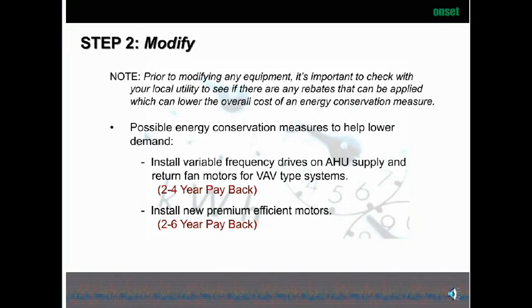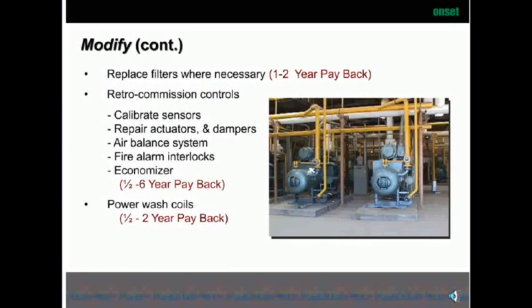One modification that's very simple and should always be done is installing new premium efficient motors. It's amazing how many older motors are still out there. If your motors have been rewound, they're at least 1 to 5 percent less efficient than the nameplate rating, so always factor that into your efficiency calculations. Replacing filters where necessary typically shows a one- to two-year payback and is very easy to do. Even in hospitals where filters are costly, the delta P or pressure drop across those filters can cost a lot of energy, making filter replacement a low-cost modification.